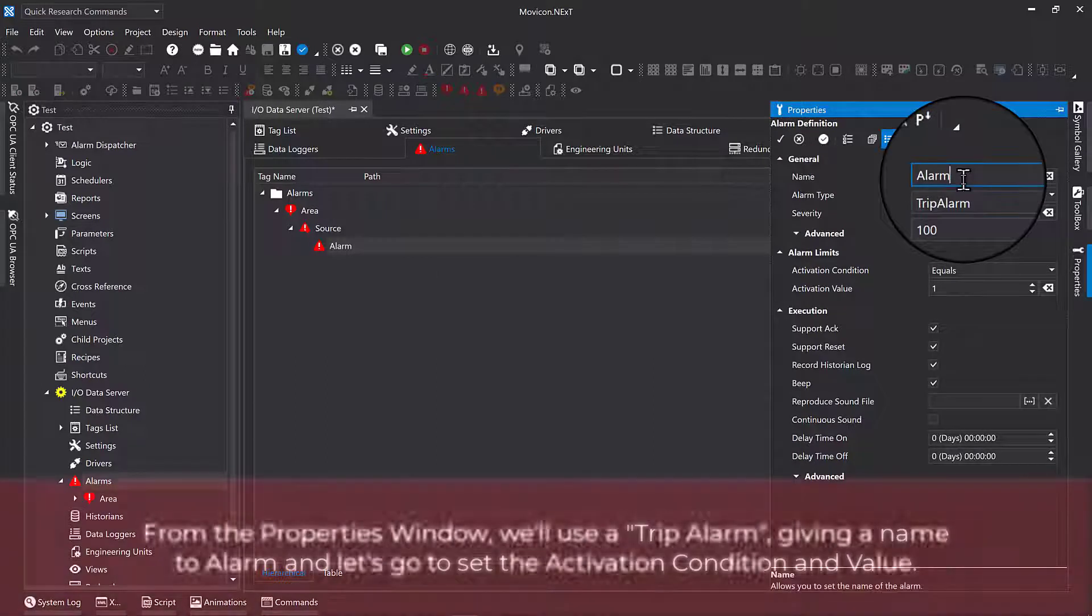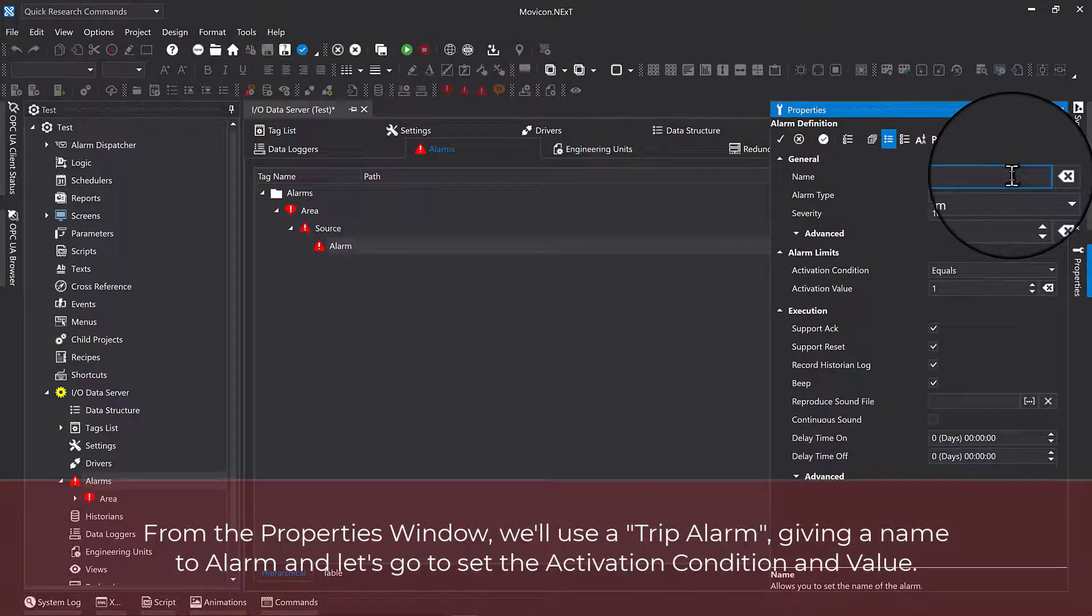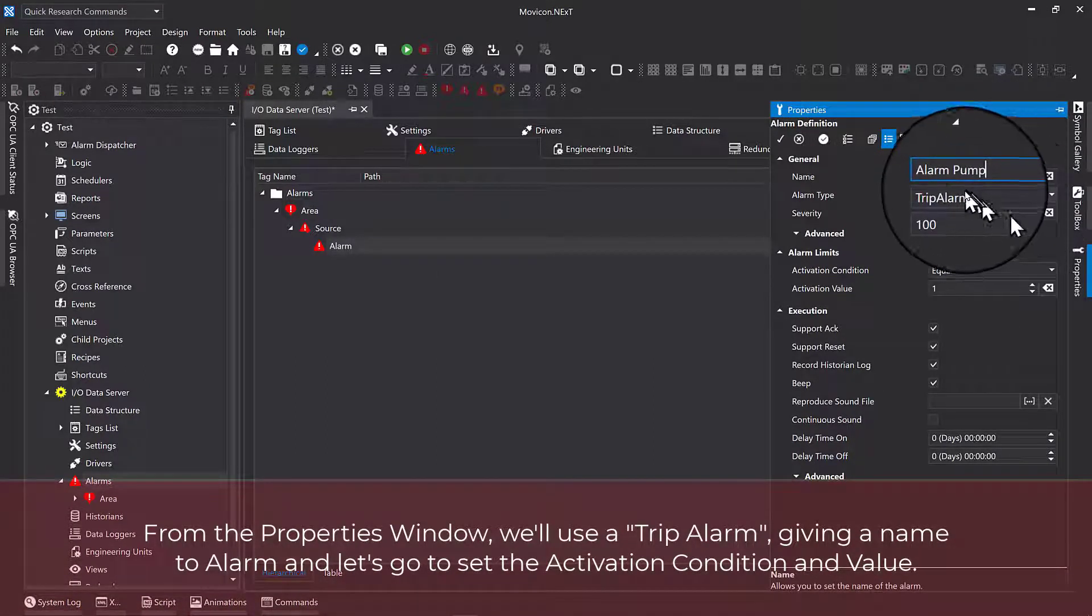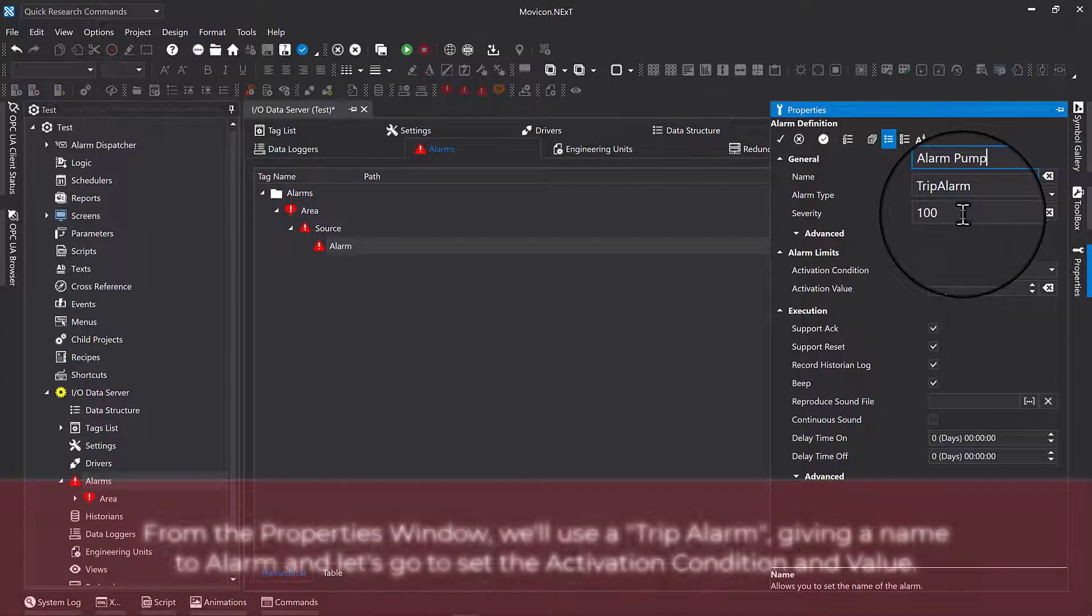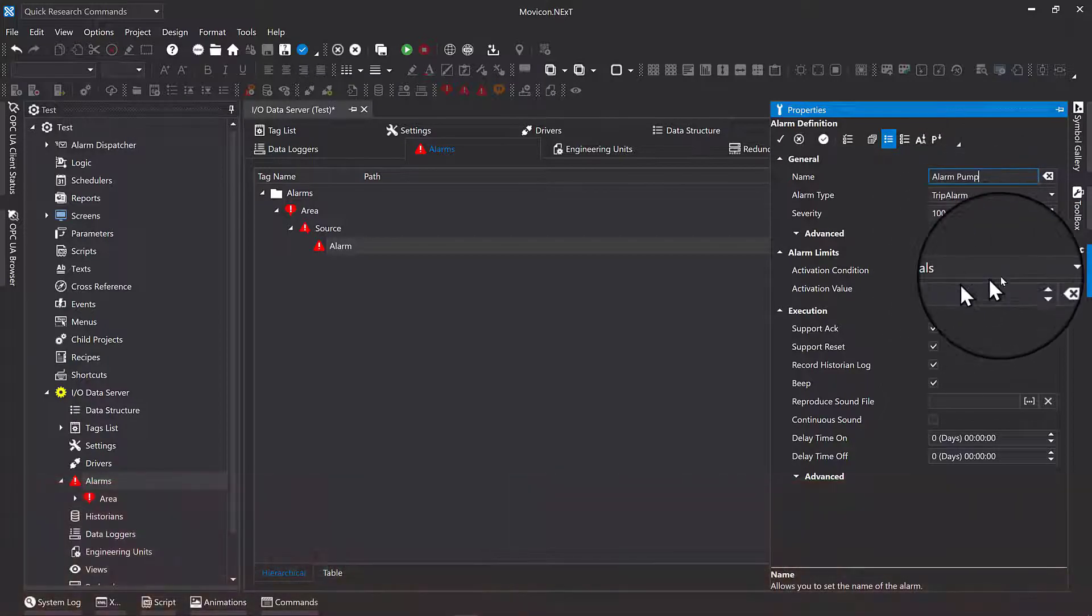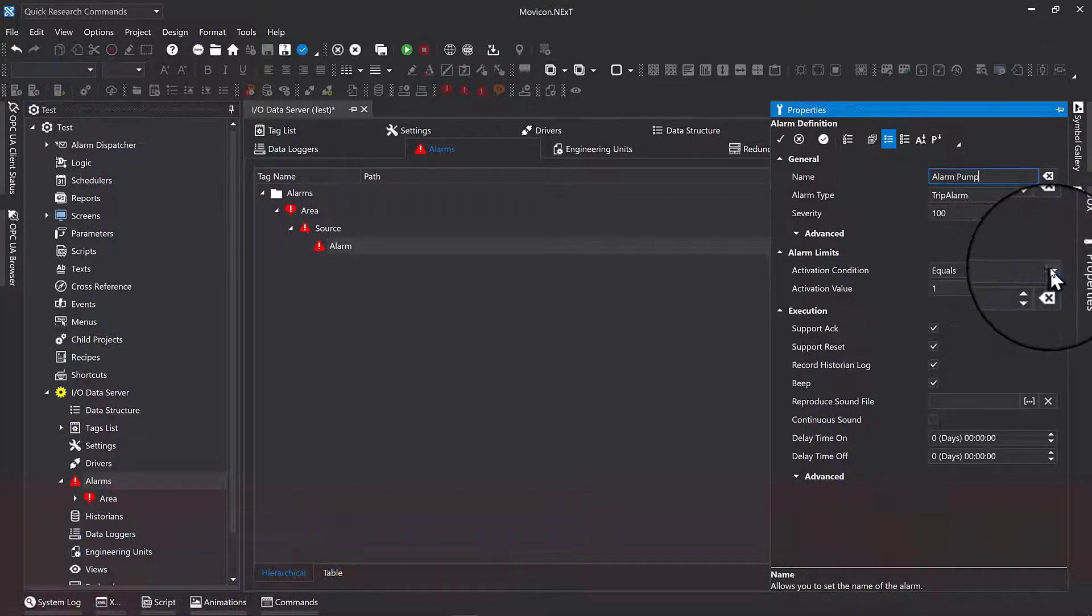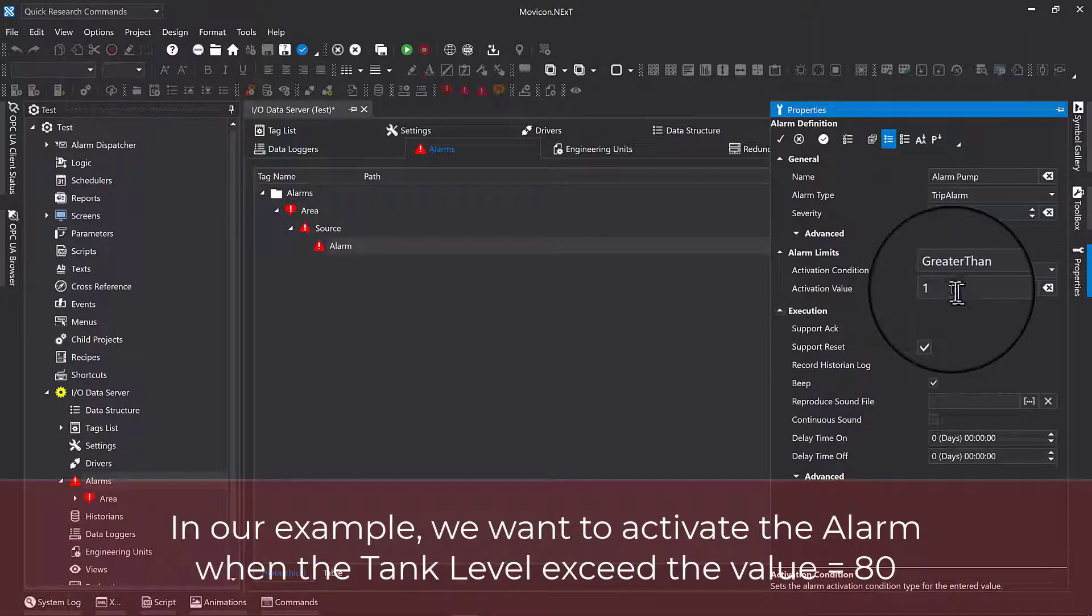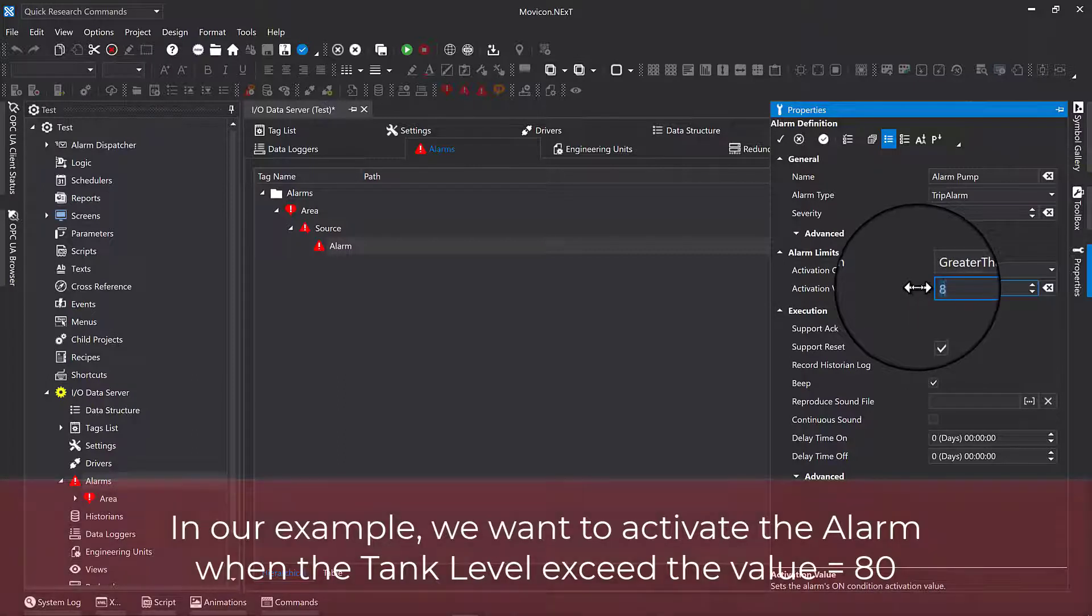From the properties window, we'll use a trip alarm, giving a name to alarm and let's go to set the activation condition and value. In our example, we wanted to activate the alarm when the tank level exceed the value equals 80.